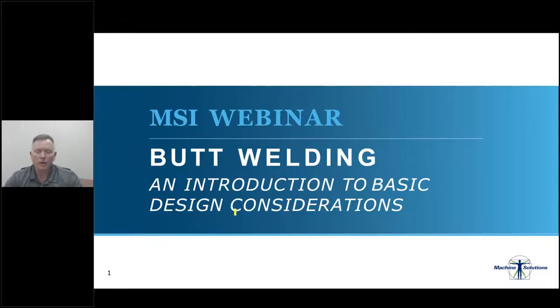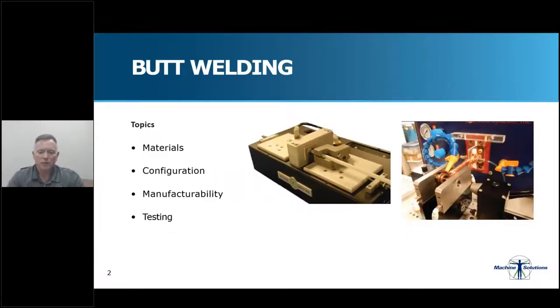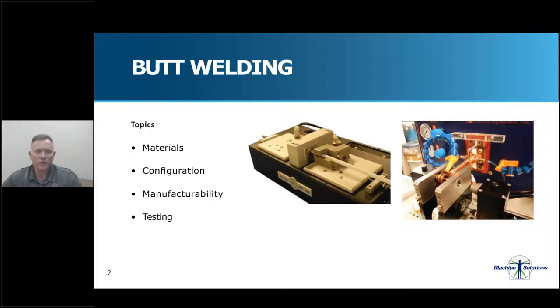Welcome to this portion of Machine Solutions' webinar on tube bonding. I'll be discussing a specific type of tube joining we refer to as butt welding. The Machine Solutions design team defines butt welding as joining the square-cut ends of two tubes together to form one continuous tube. The process uses a combination of heat, pressure, and tooling to direct and constrain the flow of melted polymer into a defined shape. This presentation covers the four main areas to consider as you design a catheter that requires a butt-welded tube section: materials of construction, configurations, manufacturability, and testing.